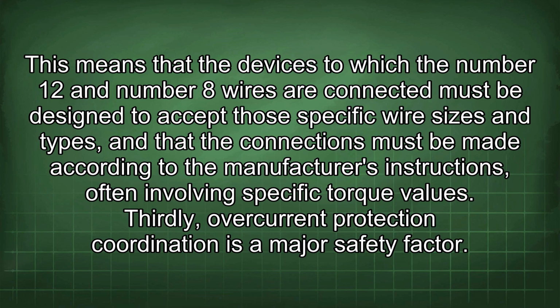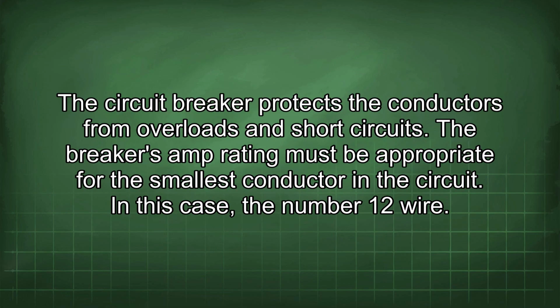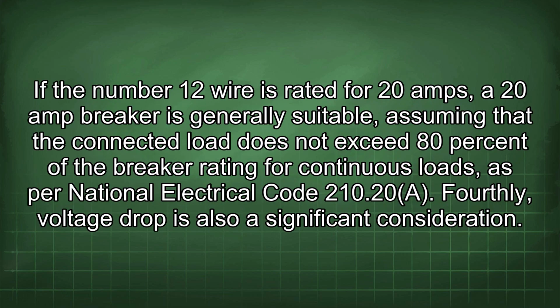Thirdly, overcurrent protection coordination is a major safety factor. The circuit breaker protects the conductors from overloads and short circuits. The breaker's amp rating must be appropriate for the smallest conductor in the circuit, in this case the number 12 wire. If the number 12 wire is rated for 20 amps, a 20 amp breaker is generally suitable, assuming that the connected load does not exceed 80% of the breaker rating for continuous loads, as per National Electrical Code 210.20(A).